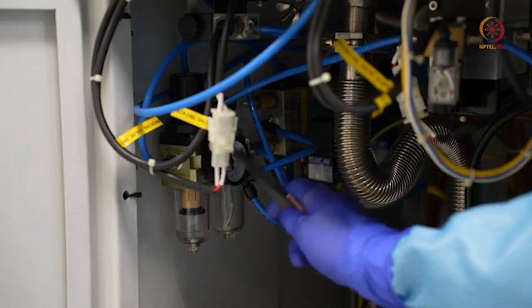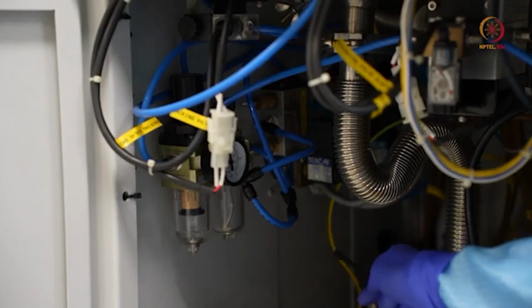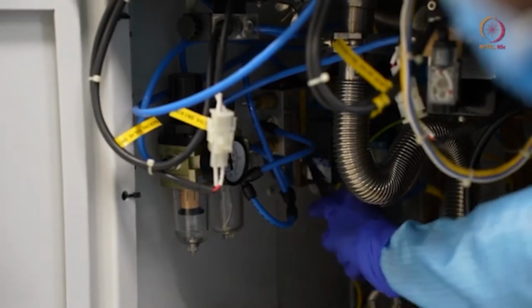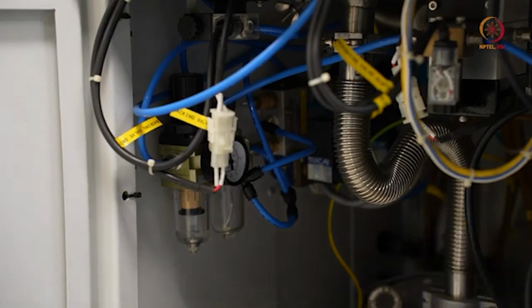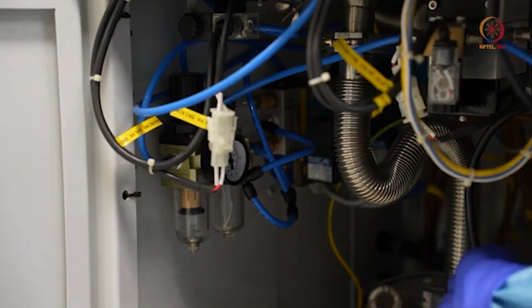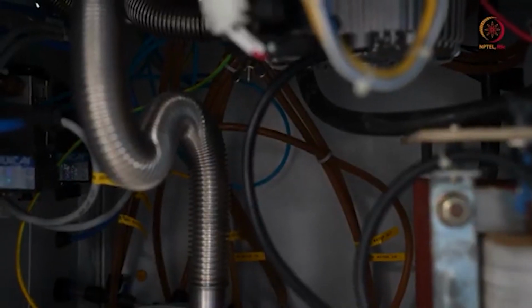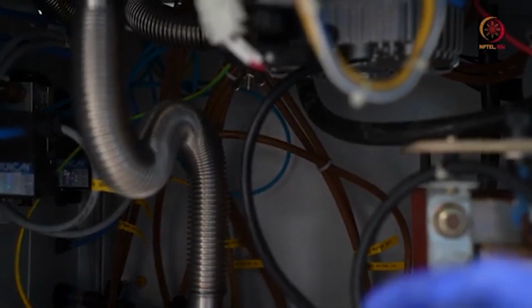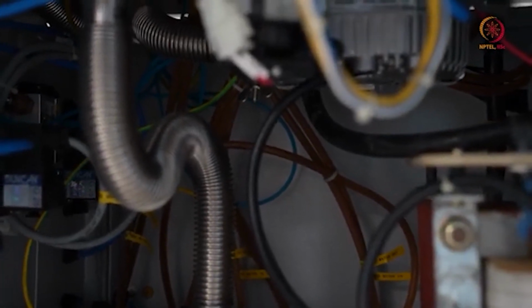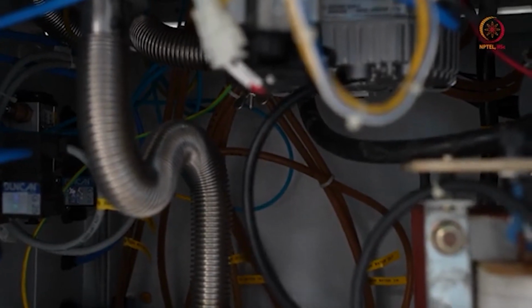If somehow the process fails, or if somehow the pump doesn't start working, you can just come and check whether this is on. And a water cooling system is also there inside, and the shutter and other things we will show inside. Those controllers are also inside, and on the backside there are water supplies. As you can see, those are the supplies for DI water. This DI water will come through the chiller so that it can always maintain a preset temperature for cooling the chamber as well as the electron beam gun.